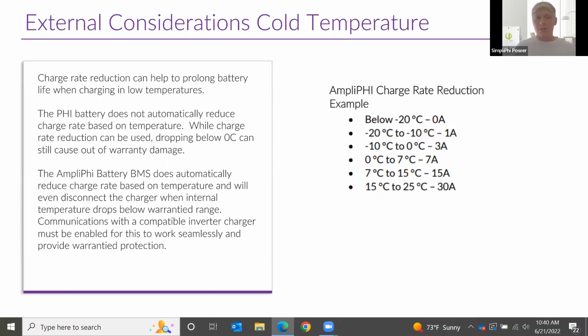Also to be considered on that type of system is how often and for how long the batteries are going to be exposed to that -20 degrees Fahrenheit. Is it just a couple mornings each year in the dead of winter, before the sun comes up for a couple of hours, that it hits -20? Then I would say no—just disable charging below freezing and don't get heaters.